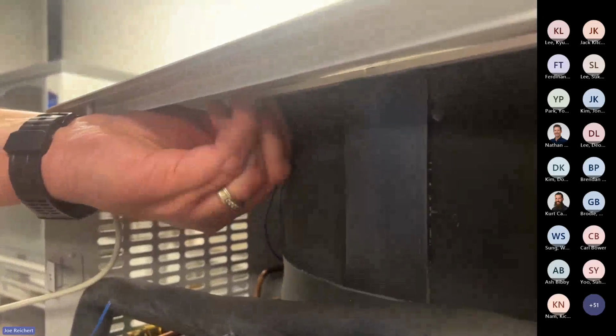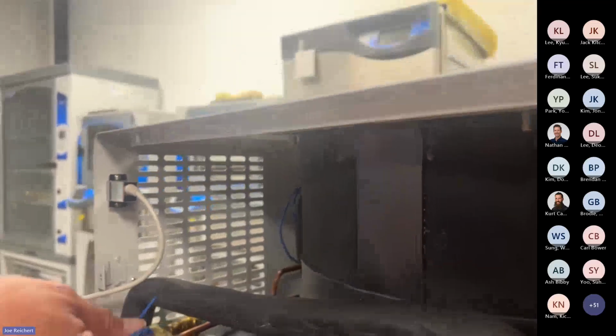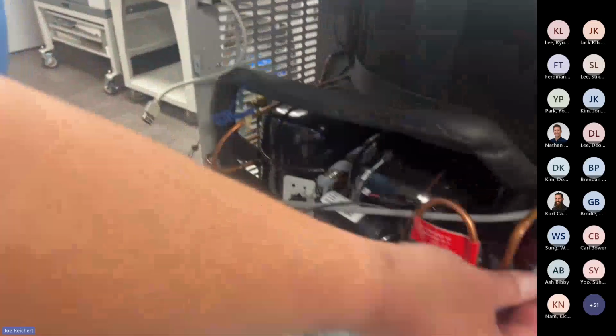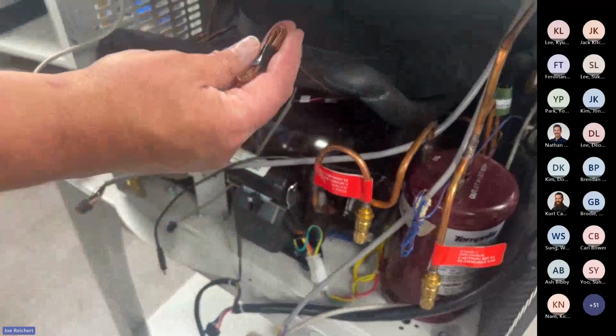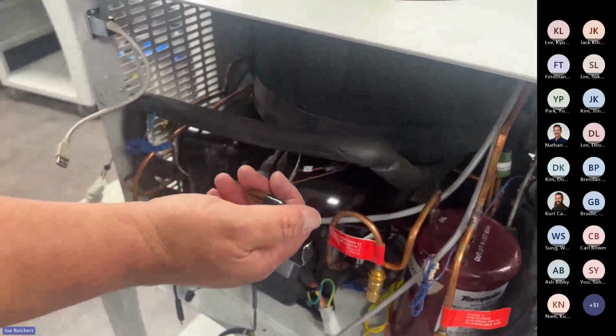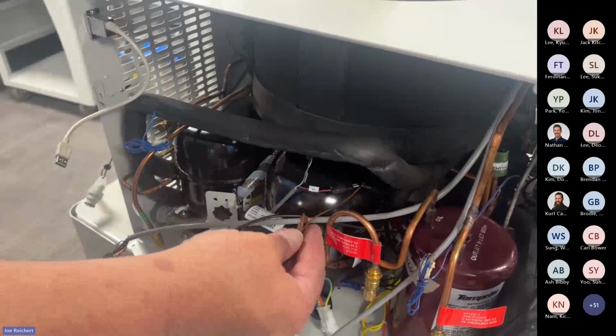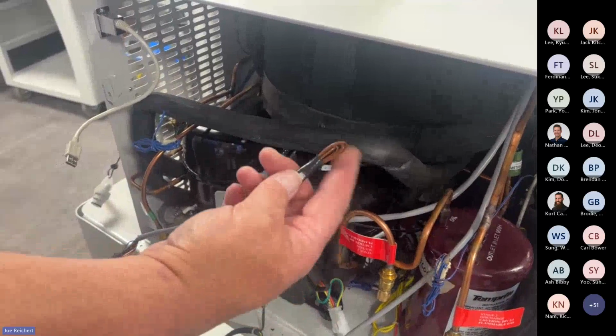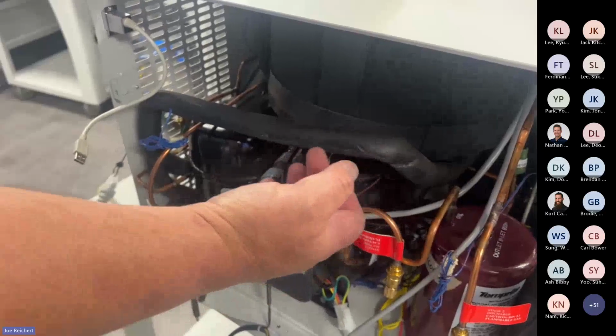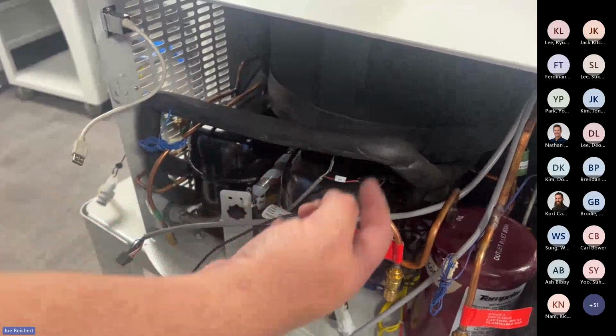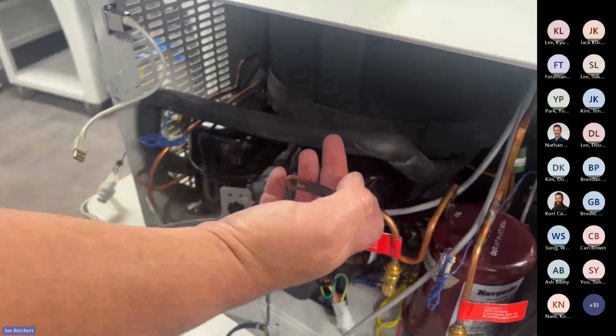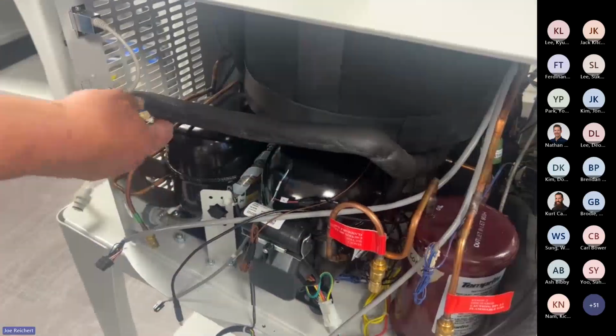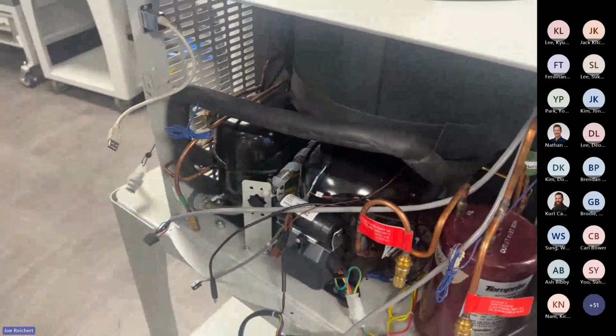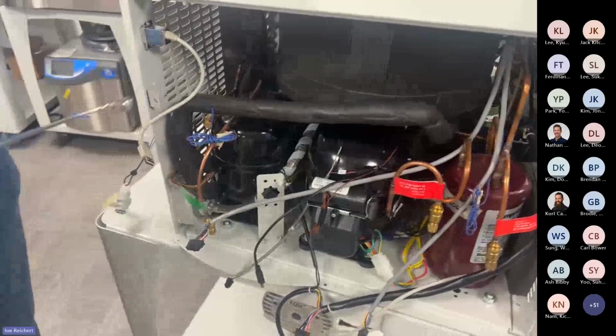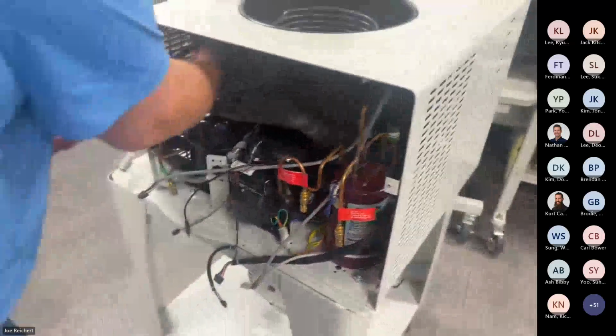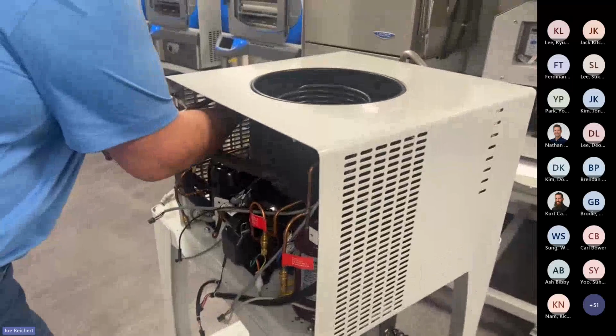Inside the machine here, we can also view our thermocouple wires. The purple ones are the thermocouples that go to the suction lines. The brown one is the one for your display. We've only used type T wires, and so your meter has to be set up to read type T. And you use these wires here to make sure your display is reading correctly. This brown one goes directly to the temperature sensor that's on the exit side of the coil. And these are going to the suction lines from the compressor. So you use those for diagnostics for your refrigeration, and the brown one for the display to make sure it's reading properly.